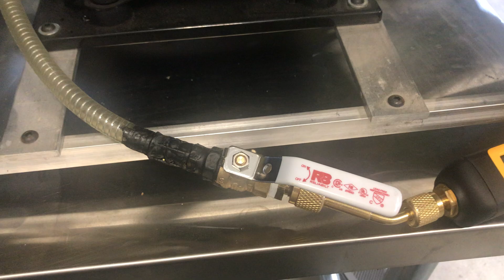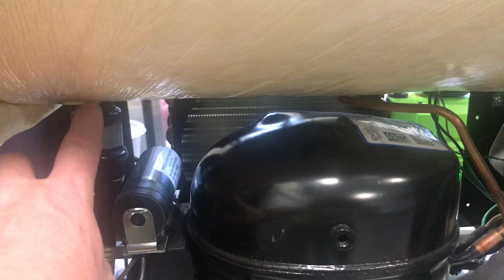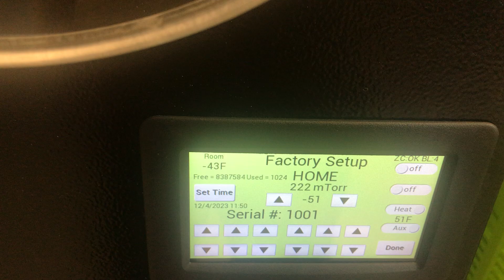Most of the time you can get away with not having to do anything like that. Just make sure that your connections here are Teflon well and clean. And then the same thing with any connections back here. Anytime I do a vacuum leak repair for customers, it's almost always just the Teflon has been pushed from the end up, and there's no thread sealing going on in the area where the threads are actually engaging. So don't overdo it with the Teflon, but put 4 or 5 wraps on there and then tighten the snot out of it and it'll be fine.